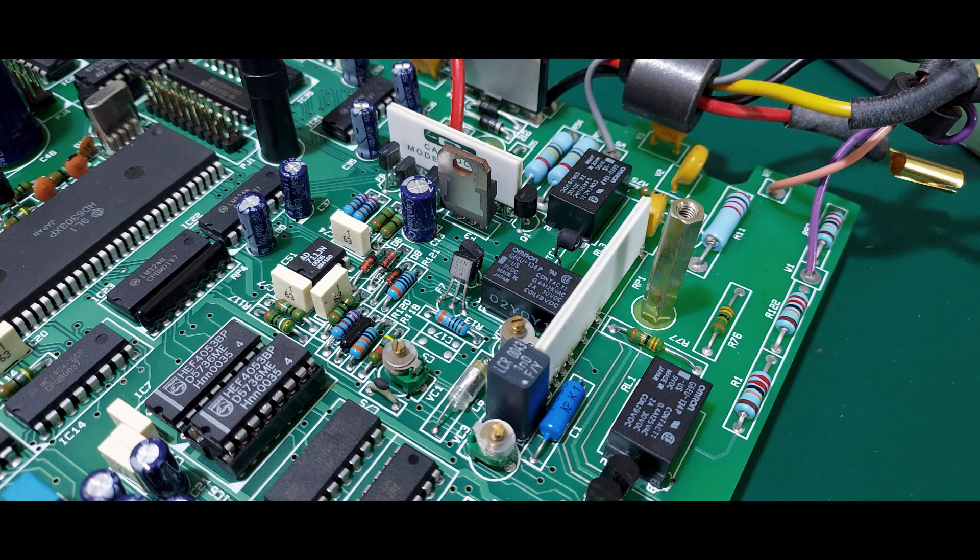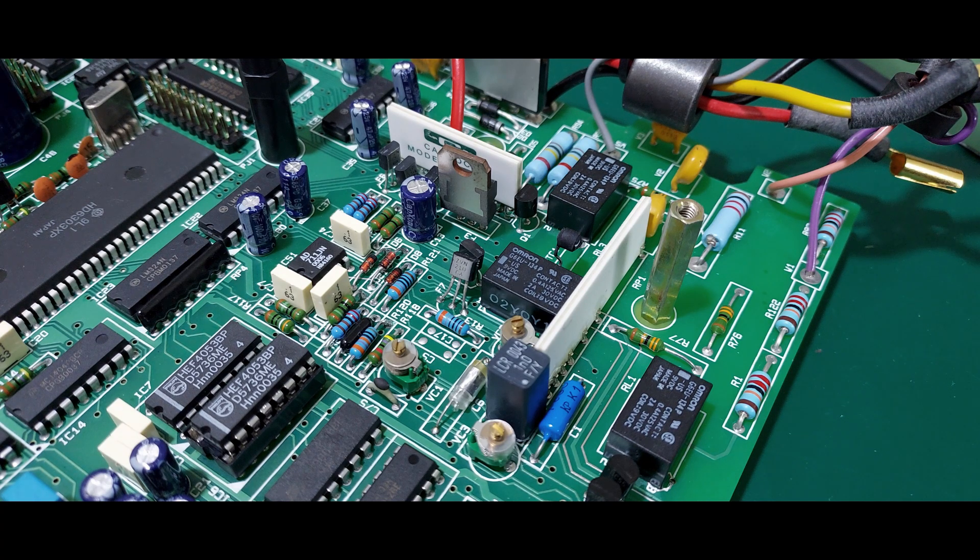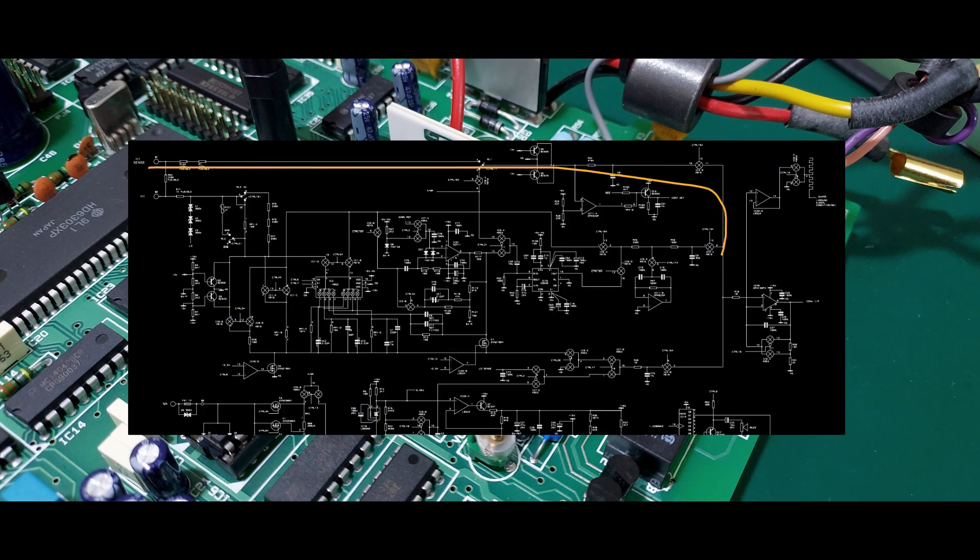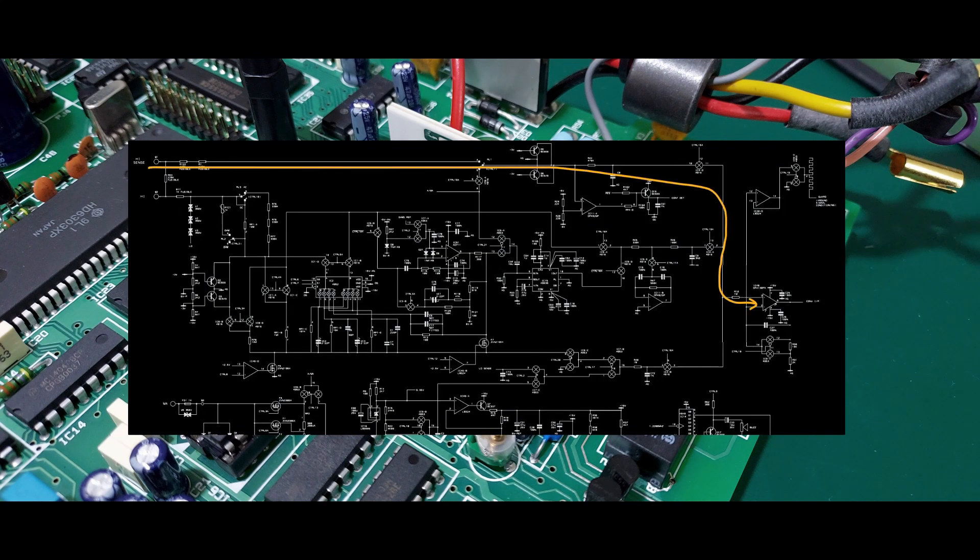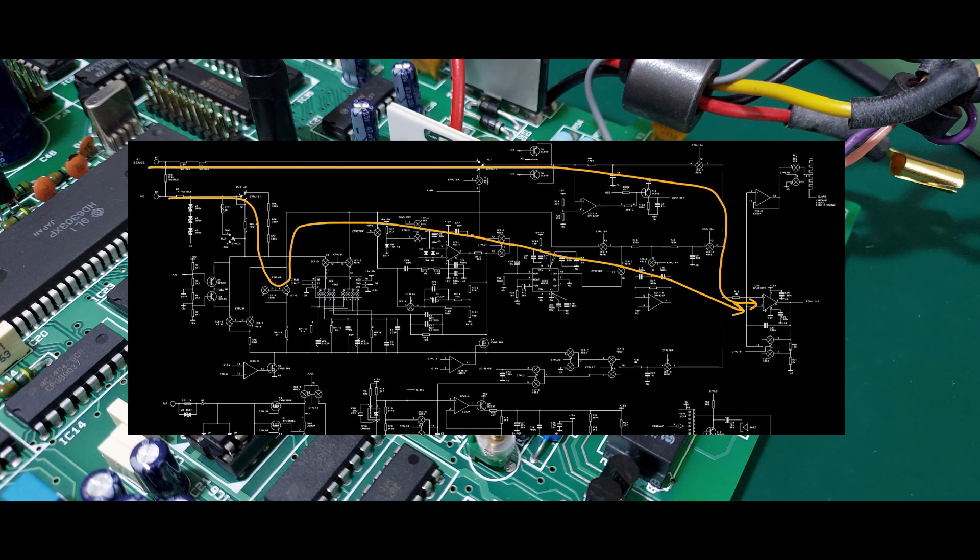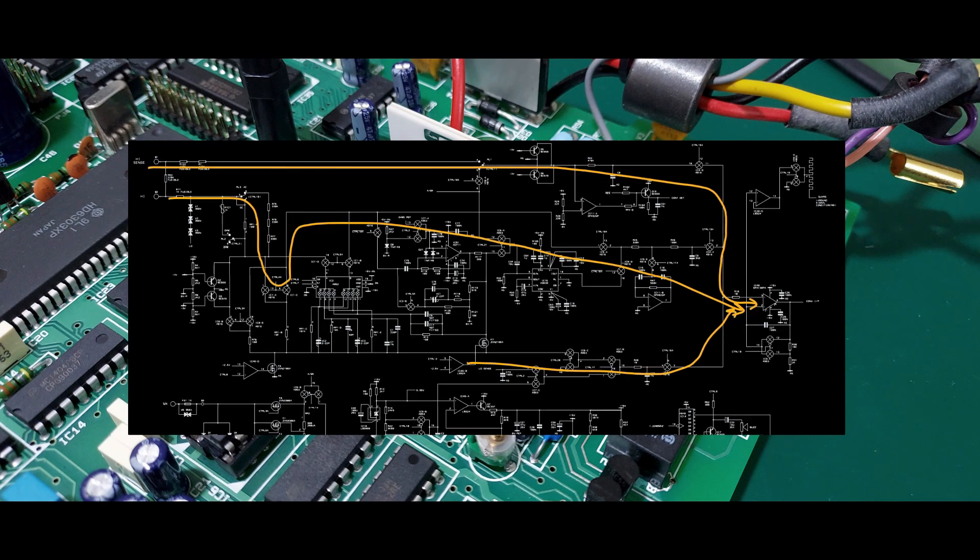First up is the input section, which has three parts. One for the low voltage ranges, one for the high voltage ranges, and one to measure ground or various fractions of the reference voltage. Most measurements require some combination of these parts to subtract offsets.